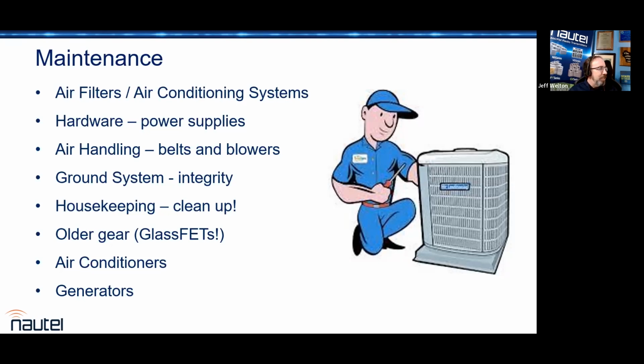But again, this is one of those things - people ask me how often they should replace fan filters, and I tell them flat out, I don't know. It depends on your site. A properly cleaned site with an air conditioner, you may replace the filters every 2 or 3 years. I've walked into sites so clean they'd taken the filters off the transmitter just to improve airflow even more. So it really depends. If you've got good double filtered exchange air with positive pressure, so you're not sucking dust in through every crack and crevice, you could go a long while before needing to swap transmitter filters. The room air filters might get changed on a much more regular basis. But one site to another, they're typically all going to be a little different, so you build the schedule based on your specific site.